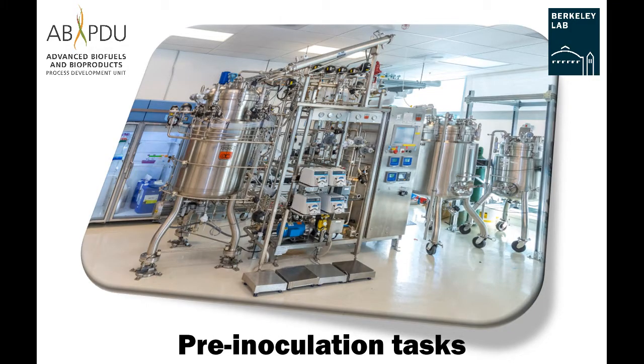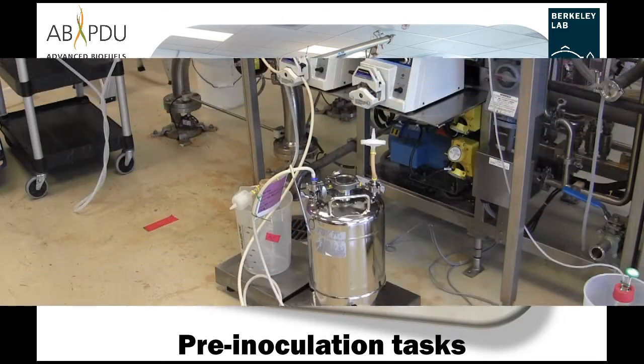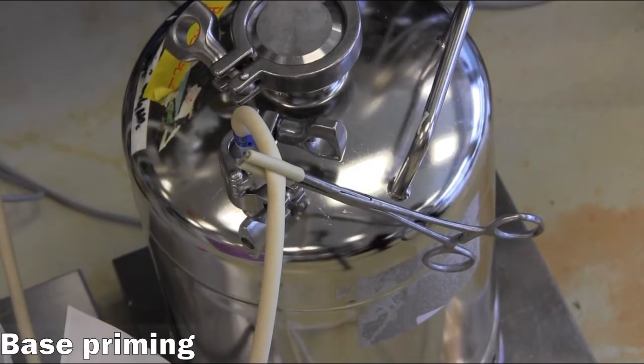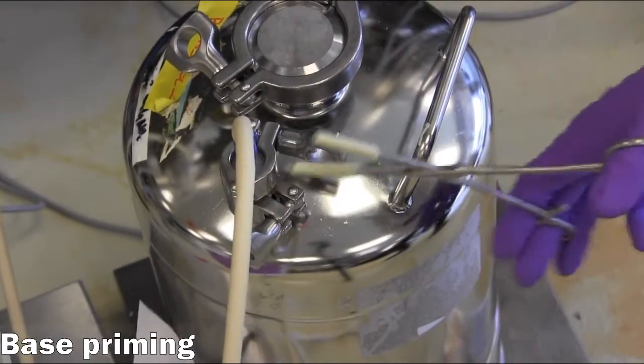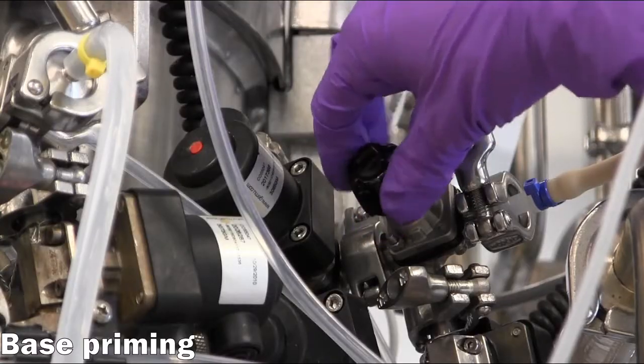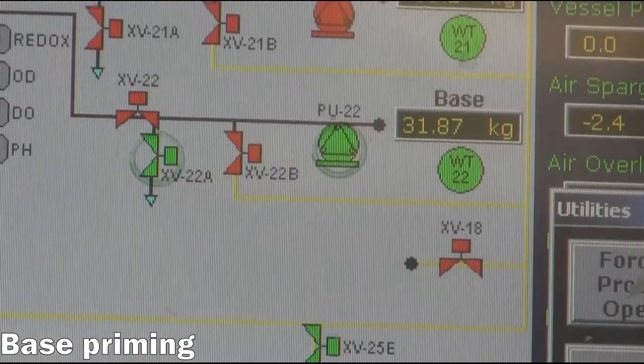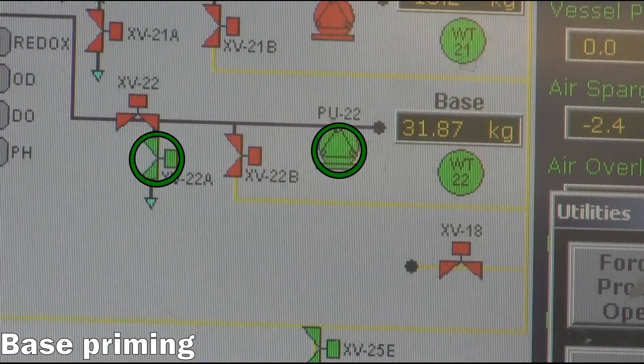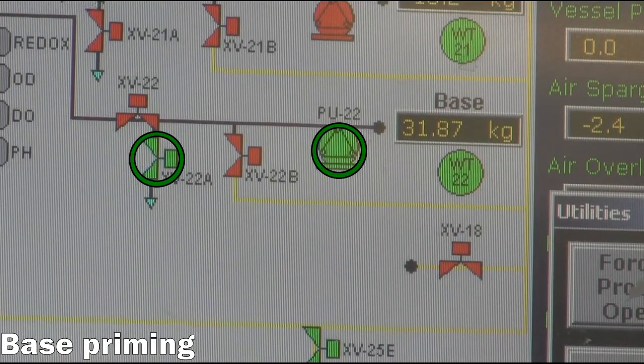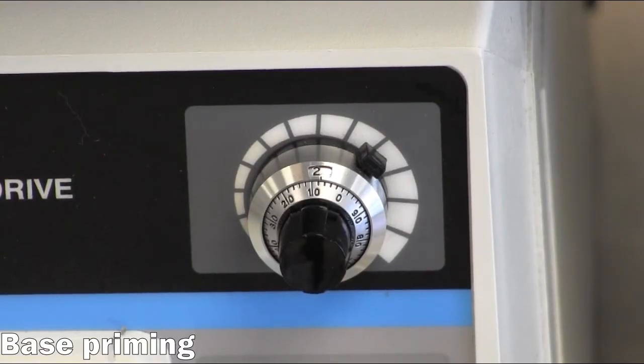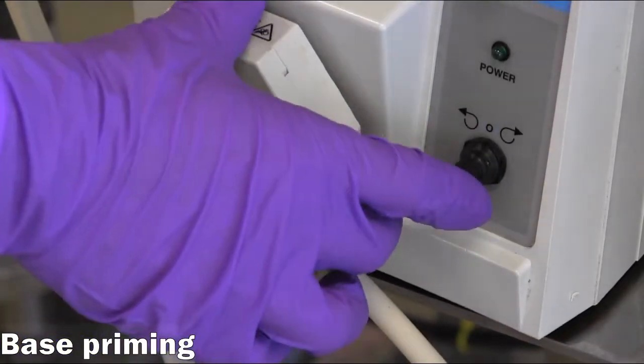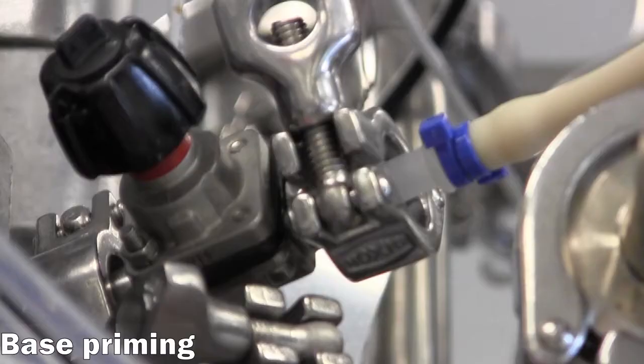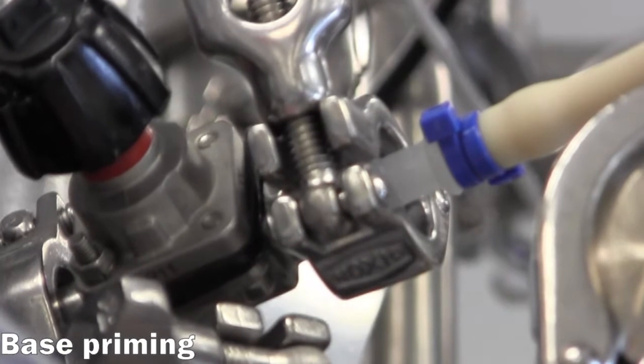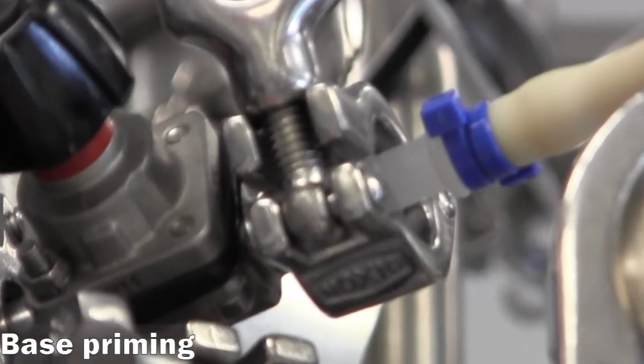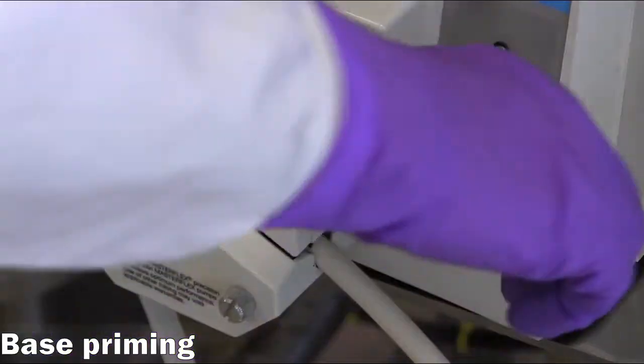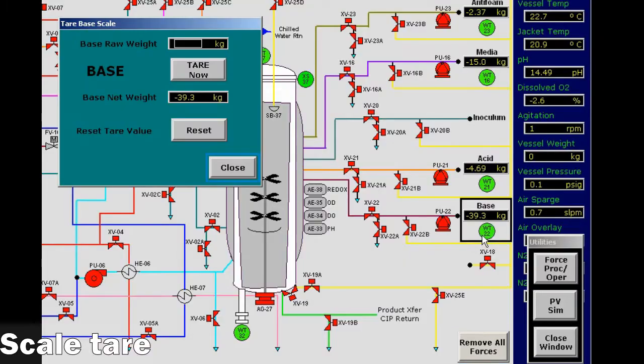Pre-inoculation tasks. Base priming. In order to prime the base line, remove the clamp from the outlet line, open the hand valve, and on the HMI, open the drain valve. Again, set the pump no higher than 2.1 and turn on. Watch the see-through hose barb until you see base come through. Turn off the pump and tare the base scale.